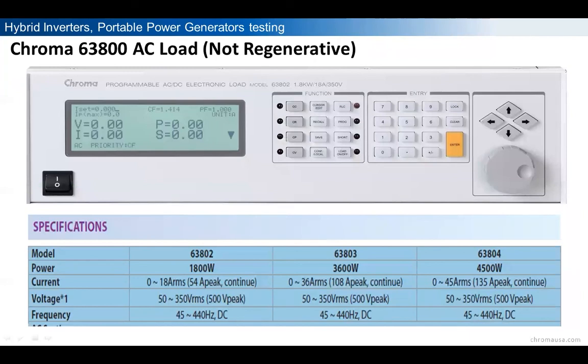Another option for this loading would be our 63800 non-regenerative load. It's a device that's been around a while, very reliable, and a little less expensive. If you're looking for a lower cost device, I recommend our 63800 AC loads. They come in 1800 watt, 3600 watt, and 4500 watt output models, vary in voltage from 50 to 350 volts, and can handle peak currents up to 135 amps. If you need higher power, they can also be paralleled.